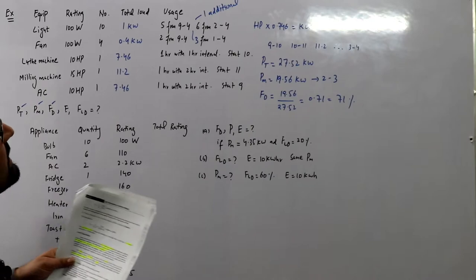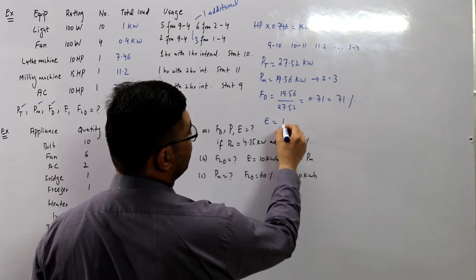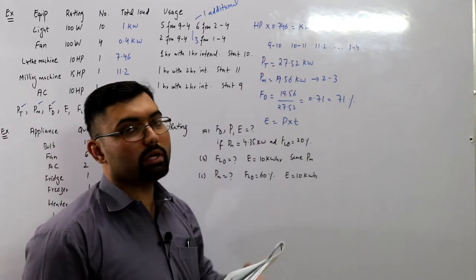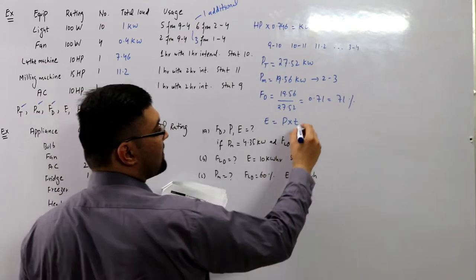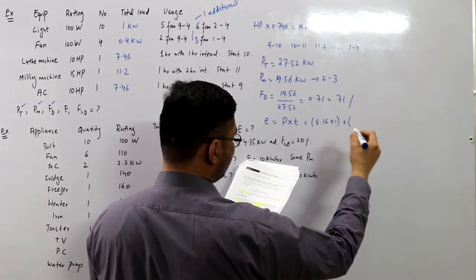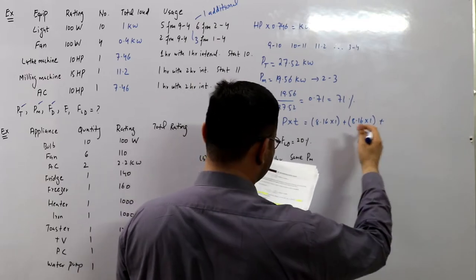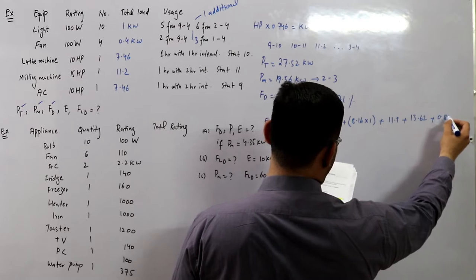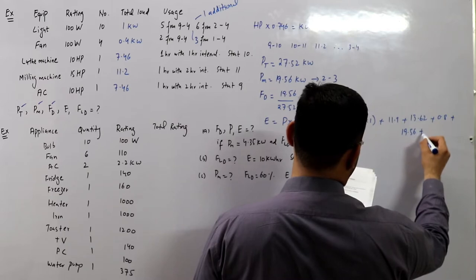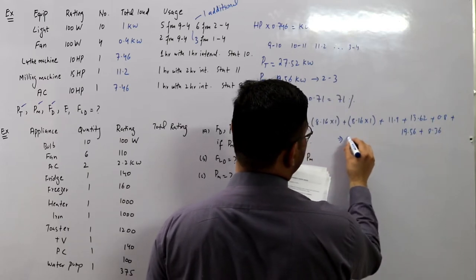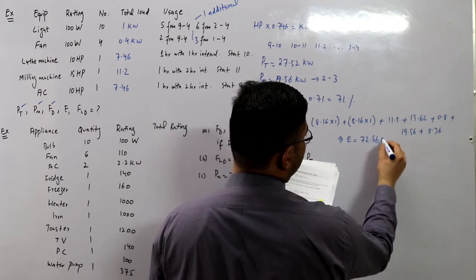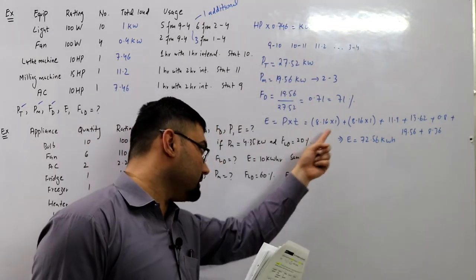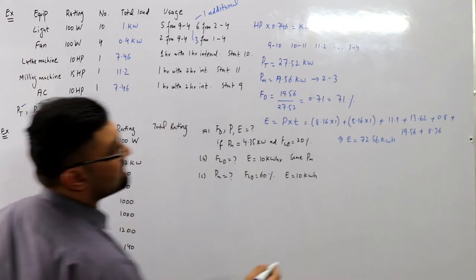The energy consumed is power multiplied by time. Drawing on an hourly basis: 8.16 × 1 + 8.16 × 1 + 11.9 × 1 + 15.62 × 1 + 0.8 × 1 + 19.56 + 8.36. The total energy units consumed comes out to be 72.56 kilowatt hours. Energy equals power into time, with time being one hour for each interval.